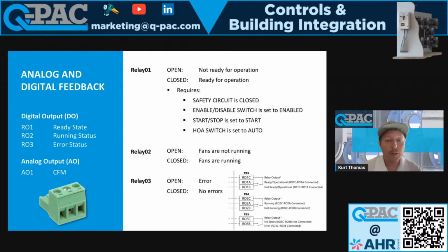So relay number 2, this is used to say, hey, you have fans that are actually spinning. You are moving air. The reason we added this is because a lot of folks are used to having VFDs and AC motors, right? And so you can send your VFD a signal, but you don't always know if the motor is actually spinning or not, right? So they would add CTs to that motor and the power wire going into that motor. So we said, hey, you don't have to do that with ours. We'll give you a relay, monitor that relay. You don't have to put a bunch of CTs on every single fan just to prove it's running. We give you that information.